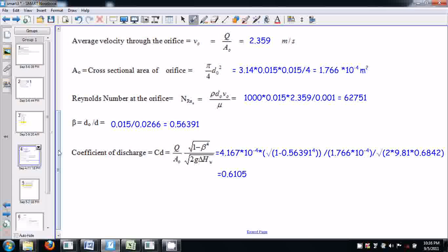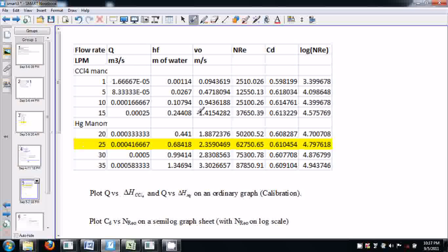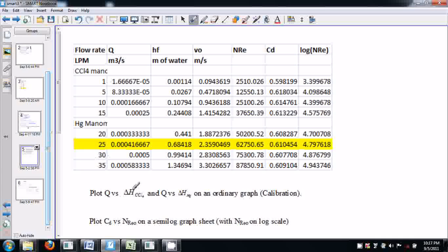The Reynolds number at the orifice is: Re = ρ·d₀·v₀/μ, where ρ is the density of the fluid, d₀ is the orifice diameter, v₀ is the velocity through the orifice, and μ is the viscosity of the fluid. Beta is the ratio of orifice diameter to pipe diameter. The coefficient of discharge is calculated using this formula. Calculate the coefficient of discharge and Reynolds number for all the flow rates.